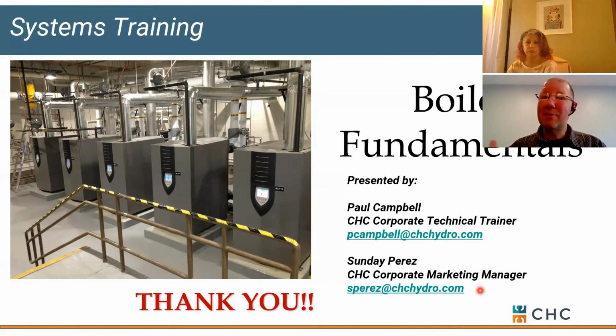If there's rebates from your utility, that might help offset that. So it really all comes down to kind of comfort level, maintenance requirements, existing equipment, as well as what your actual site conditions are. So do I encourage condensing boilers? There's some safety there, but they don't always make sense. If you're running warm returns, you're not going to get a payback on a condensing boiler unless the utility is helping you with that, or you can justify it based on some cold starts in your system. But on the domestic side, that tends to be pretty stable as far as return temperatures go. Another good question.